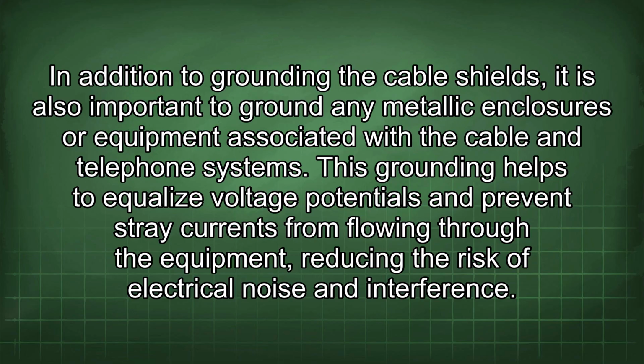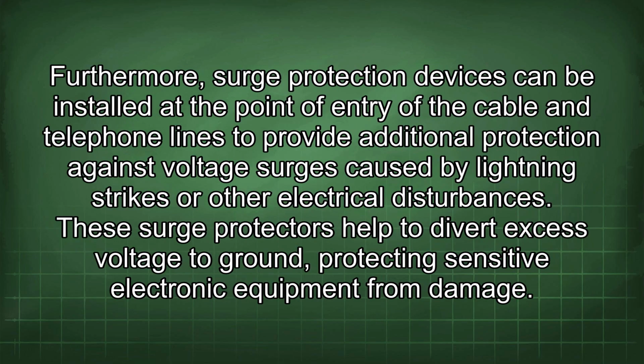electrical noise and interference. Furthermore, surge protection devices can be installed at the point of entry of the cable and telephone lines to provide additional protection against voltage surges caused by lightning strikes or other electrical disturbances. These surge protectors help to divert excess voltage to ground, protecting sensitive electronic equipment from damage.